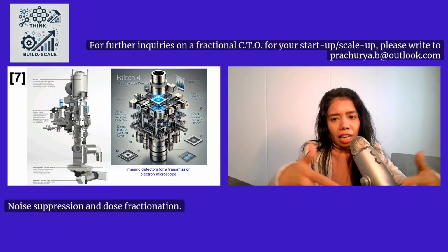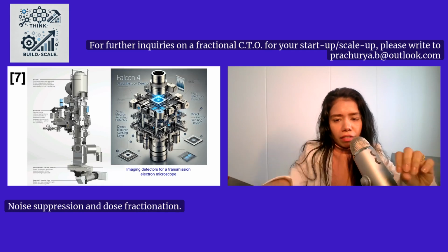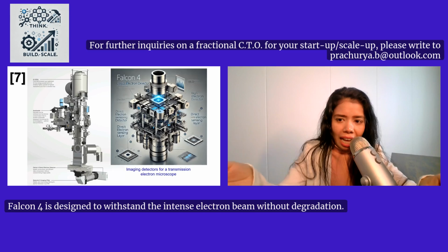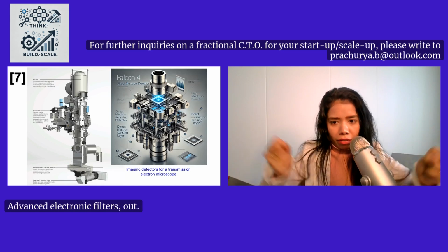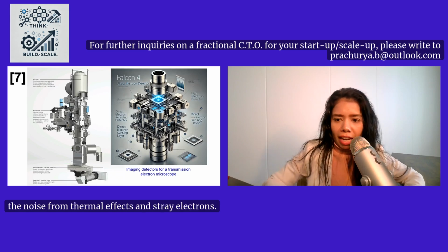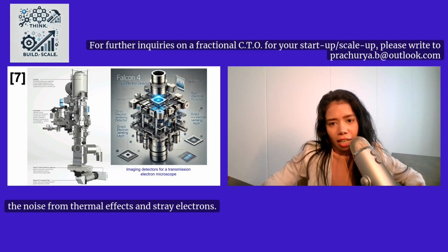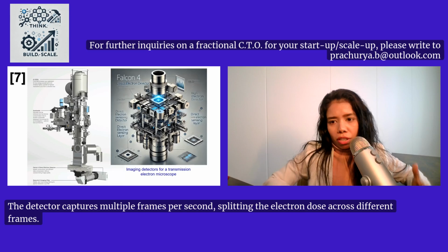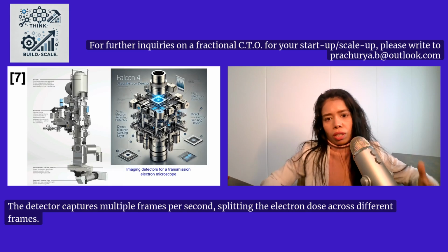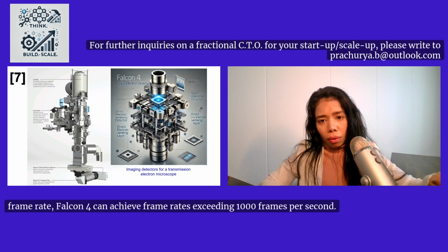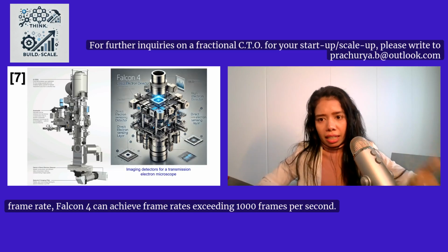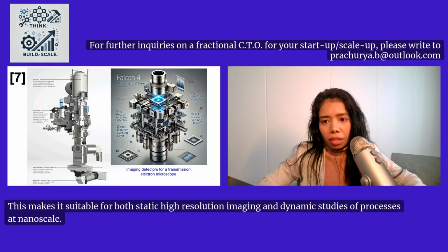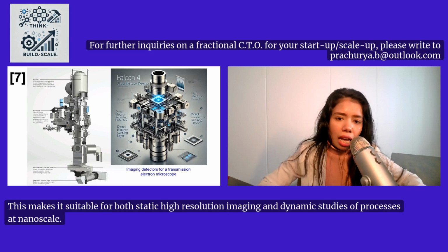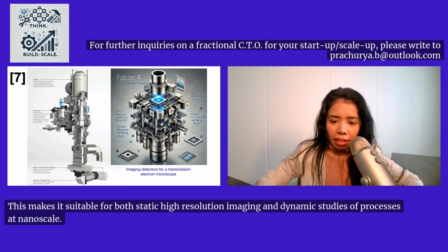Noise suppression and dose fractionation. Falcon 4 is designed to withstand the intense electron beam without degradation, and advanced electronics filter out the noise from thermal effects and stray electrons. The detector captures multiple frames per second, splitting the electron dose across different frames. Frame rate. Falcon 4 can achieve frame rates exceeding 1000 frames per second. This makes it suitable for both static high-resolution imaging and dynamic studies of processes at nanoscale.